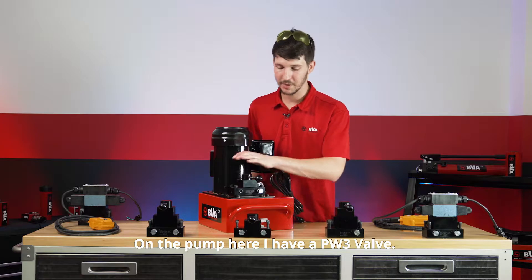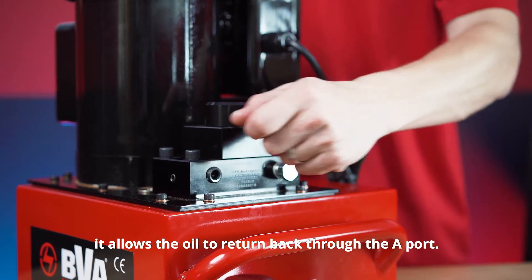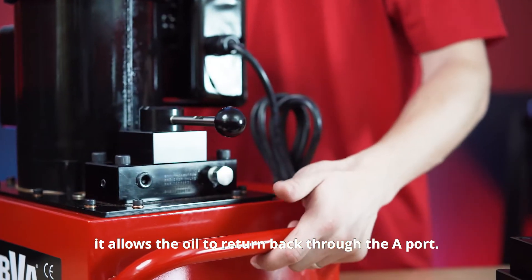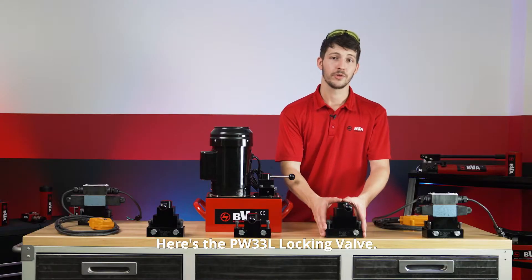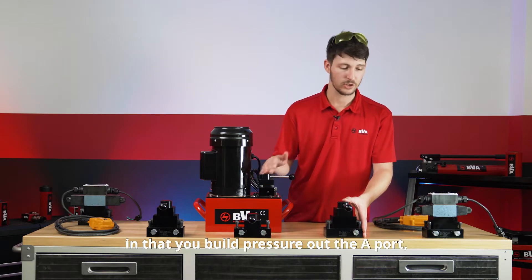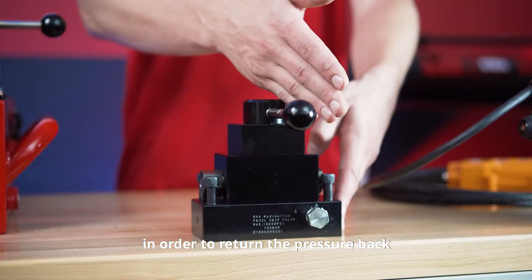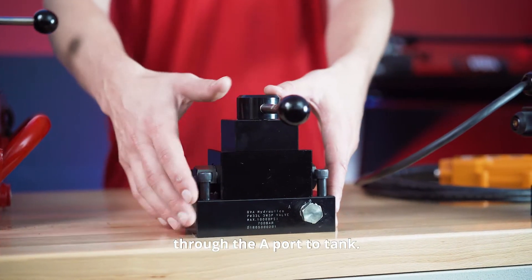On the pump here I have a PW3 valve. This valve allows you to build pressure out the A port, but then when you move it to the B port it allows the oil to return back through the A port. Here's the PW3L locking valve. It is similar to the PW3 valve in that you build pressure out the A port, but it requires you to move to the B port in order to return the pressure back through the A port to tank.